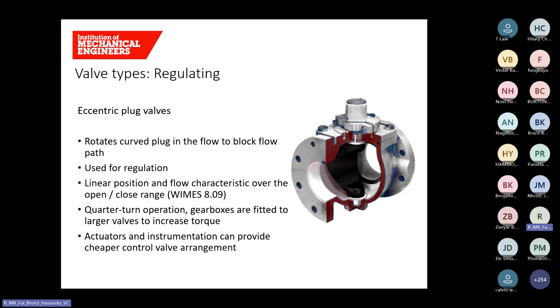From the outside, it looks sort of like a ball valve, but inside, instead of using a ball, it uses a curved disc. And the profile of this disc as it opens and closes into the flow path means that the relationship between valve position and flow, or valve position and head loss, is quite linear across the operating range. It's a quarter turn valve, and it can be used with a gearbox for high torque or high pressure applications, or it can also be used with an actuator in a control system.